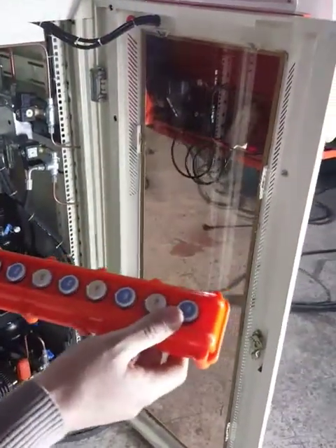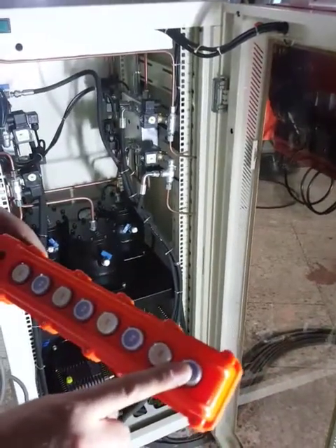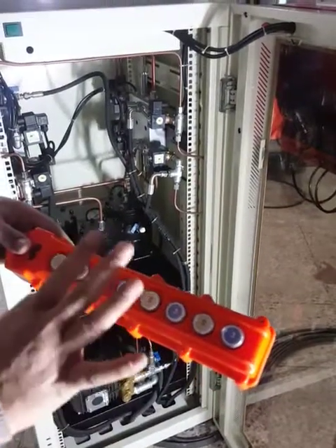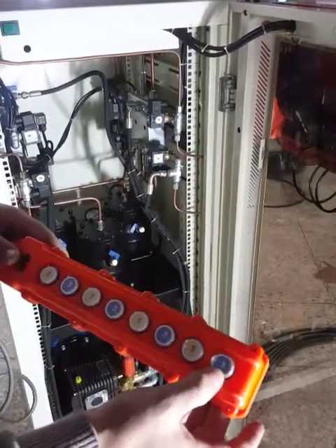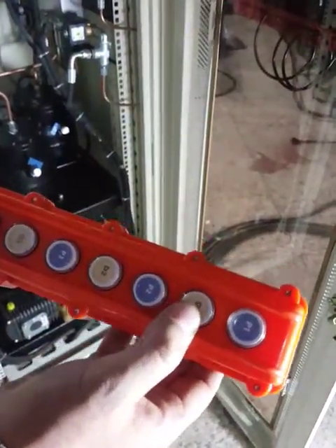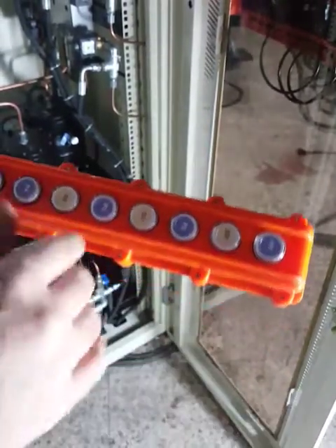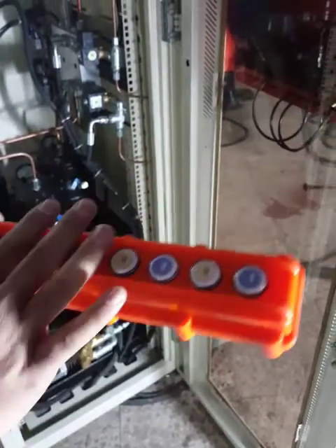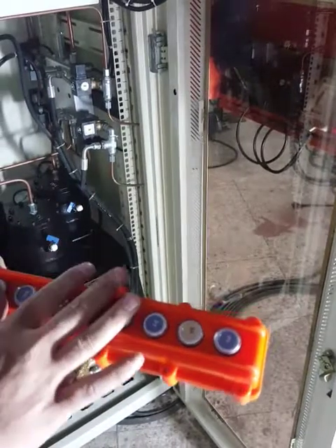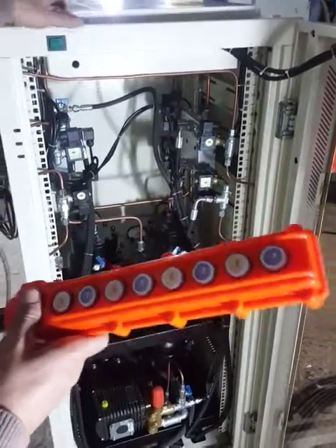In the front, the machine has a handy keyboard for manual control of each line. Each line includes a pressurizing and drain key. It has four channels — P1 is for pressurizing the first channel, and the drain key depressurizes the first channel. The same keys are available for the other three channels. The operator will use this handy keyboard for filling the sample when starting the test.